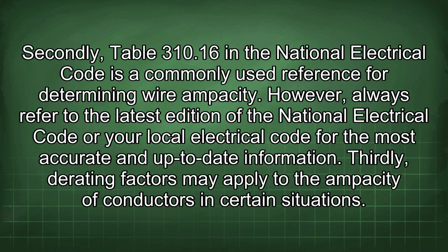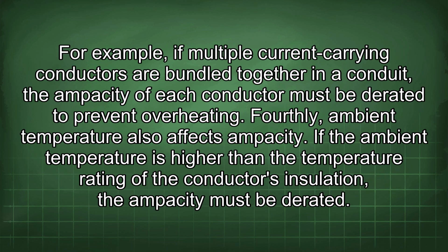However, always refer to the latest edition of the National Electrical Code or your local electrical code for the most accurate and up-to-date information. Thirdly, derating factors may apply to the ampacity of conductors in certain situations. For example, if multiple current-carrying conductors are bundled together in a conduit, the ampacity of each conductor must be derated to prevent overheating. Fourthly, ambient temperature also affects ampacity. If the ambient temperature is higher than the temperature rating of the conductor's insulation, the ampacity must be derated.